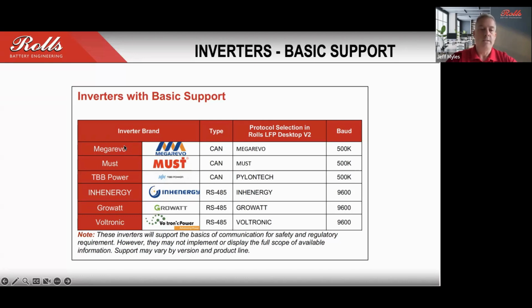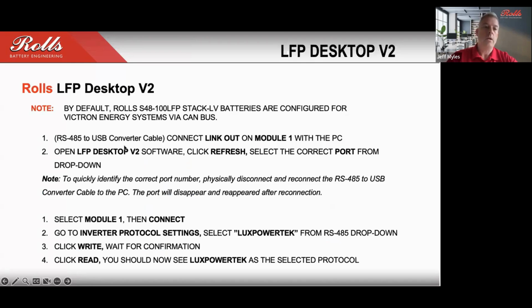When you are connecting to the unit and setting up the protocol, in some cases there may be a particular protocol listed, and for example, the protocol may be listed with an RS-485 type connection or with CAN. So it's important that you pick the appropriate one based on the particular inverter that you're working with and what that inverter requires. When you're setting up the protocol, there are two different ways to do this.